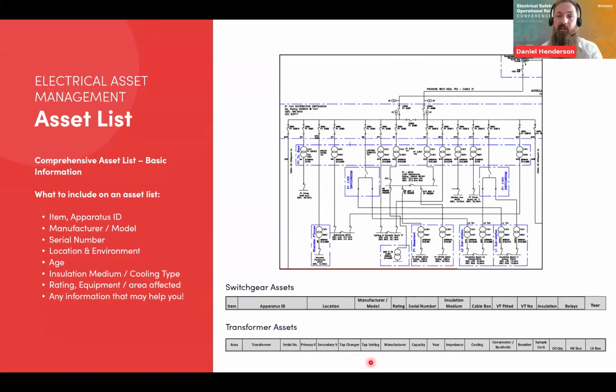The tap setting: it's probably something you'll seldom use, having the actual tap setting on an offload tap changer recorded, but there might be instances where you have to parallel transformers, or have one transformer feeding a common board during a maintenance outage, for example, or if you have voltage management issues, i.e. over voltage or under voltage on the end application. Again, it's a good reference, especially when you've got a wide geographical spread.